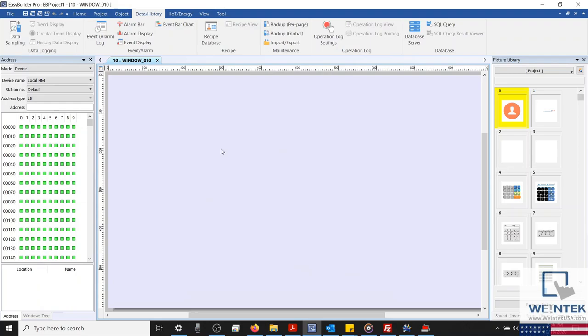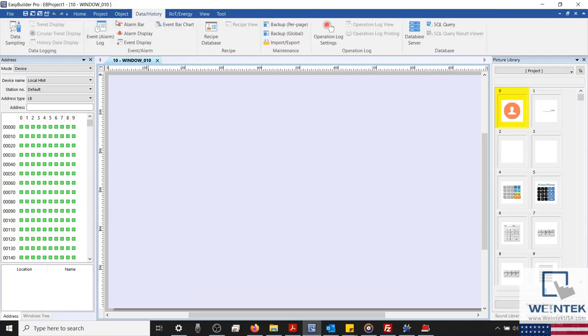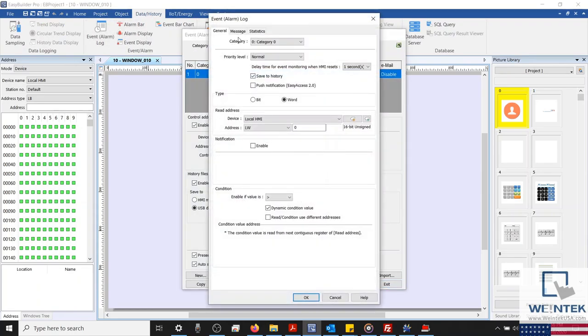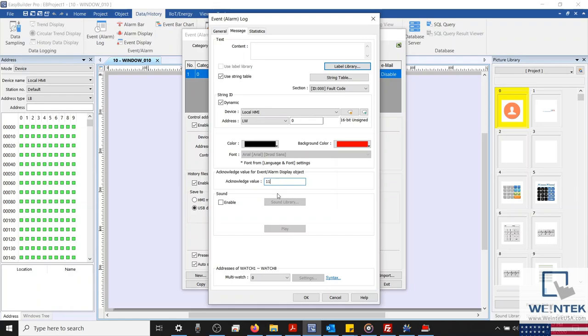An alarm's acknowledge value is used within an alarm or event display object's acknowledge register. The acknowledge value corresponds to a window that will be used to display a message. For example, if I leave 11 as my acknowledge value, and I use an indirect window with my alarm object, and the register used within the indirect window is also my acknowledge register, then window 11 can be used to display helpful information related to this alarm. During this demonstration, we'll use window 11 to display alarm information, so let's leave our acknowledge value at its default setting.